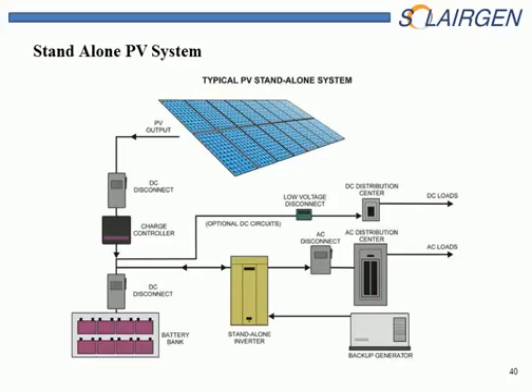The DC distribution center may or may not be in one of these systems. Some of these customers have DC loads, most of them do not. So more than likely what you're going to have is the AC distribution center. You'll have one AC panel located in a typical place inside the house, and you should have an AC disconnect located outside or a plaque indicating where it is. Since this is not a grid-connected system, if it's standalone, the utility's not going to have any enforcement to say, hey, you need to pull that AC disconnect outside. It's up to the local authority having jurisdiction, and they may not have any idea where that AC disconnect should be on the outside. So there may not be a plaque, and there may not be an AC disconnect, although it's required. So if you saw a PV system and you don't see an AC disconnect on the outside, you've got a problem. You're looking at the garage possibly, or the basement, if you can get to it, to turn these systems off.